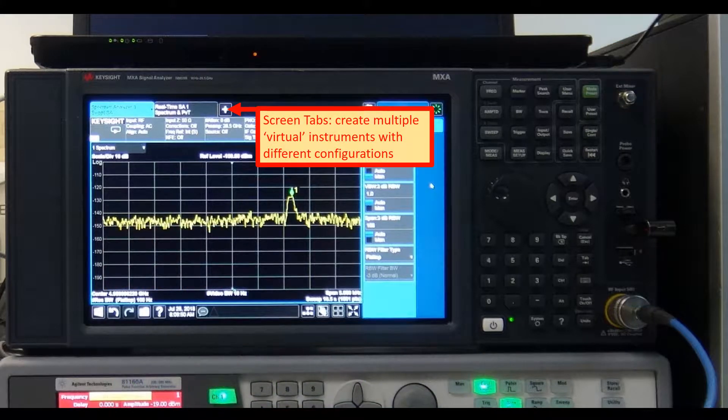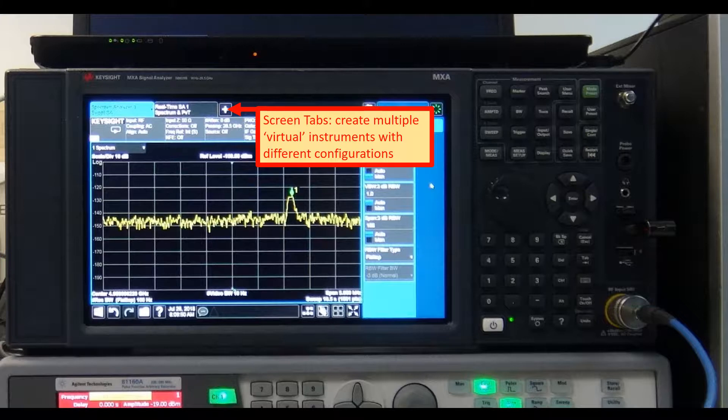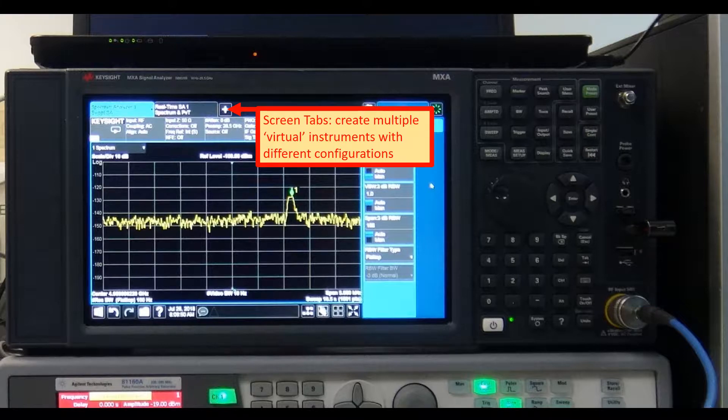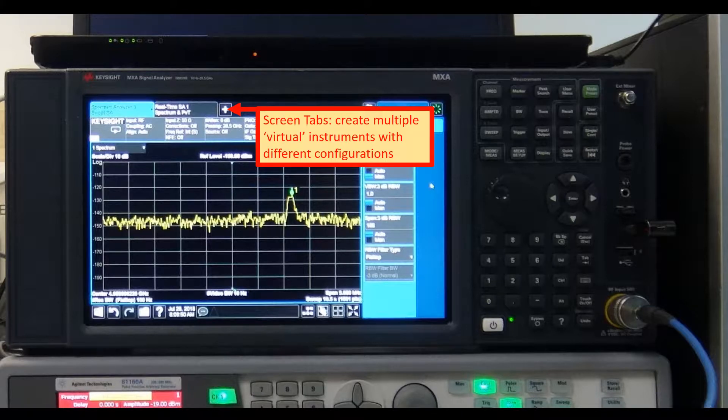Along the top of the display are tabs, one for each measurement screen you have defined. We can tap the plus sign to clone the current measurement, which can be changed afterwards for a new configuration, in a way that is very similar to an Internet Navigator. You can have up to 16 measurement tabs, but only 6 can be viewed at one time.